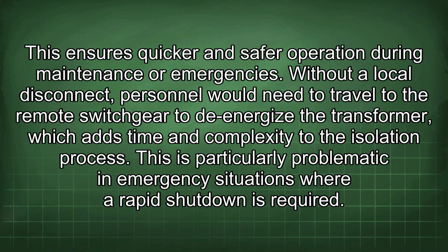Without a local disconnect, personnel would need to travel to the remote switchgear to de-energize the transformer, which adds time and complexity to the isolation process. This is particularly problematic in emergency situations where a rapid shutdown is required.